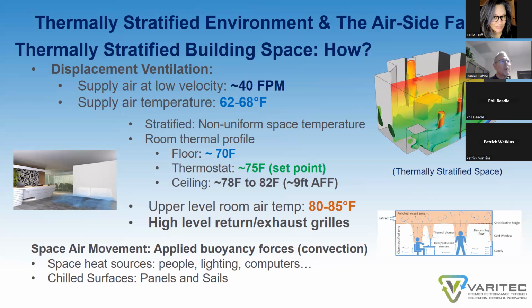to maintain a room at 75 degrees, the thermally stratified profile looks like this. The floor temperature is about 70 degrees. The ceiling temperature is about 78 to 82 degrees for a 9-foot ceiling. So consequently, you have a thermal profile in the space that maximizes the delta T at the radiant device. The upper room levels can see up to 80 to 85 degrees where the air is exhausted from a building.